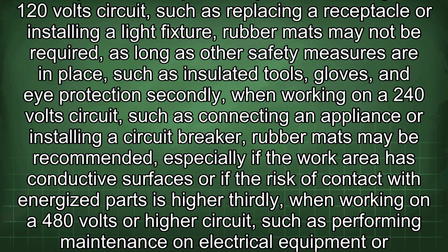Secondly, when working on a 240-volt circuit, such as connecting an appliance or installing a circuit breaker, rubber mats may be recommended, especially if the work area has conductive surfaces or if the risk of contact with energized parts is high. Thirdly, when working on a 480-volt or higher circuit, such as performing maintenance on electrical equipment or troubleshooting a fault, rubber mats are almost always required, along with other personal protective equipment and safe work practices.